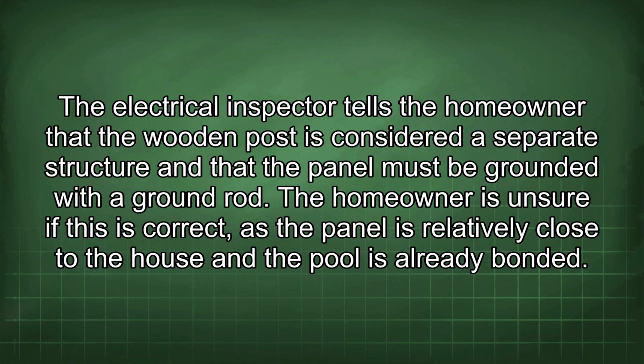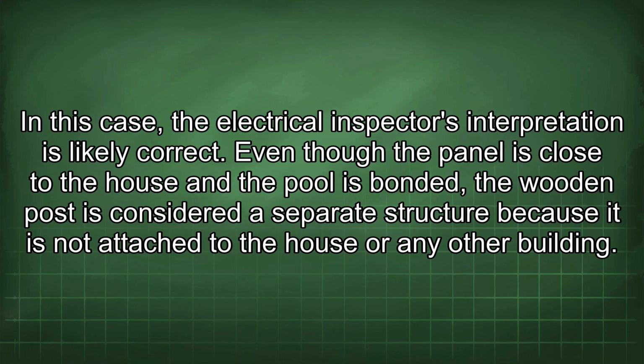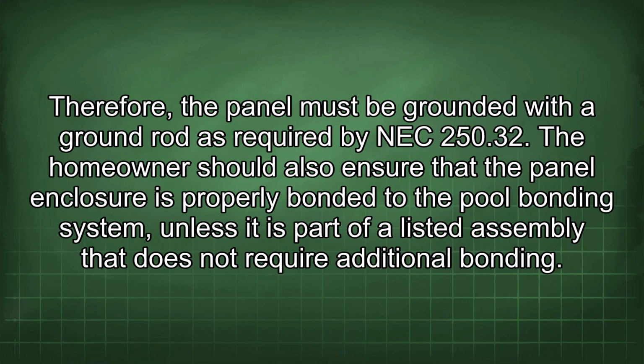The homeowner is unsure if this is correct, as the panel is relatively close to the house and the pool is already bonded. In this case, the electrical inspector's interpretation is likely correct. Even though the panel is close to the house and the pool is bonded, the wooden post is considered a separate structure because it is not attached to the house or any other building.